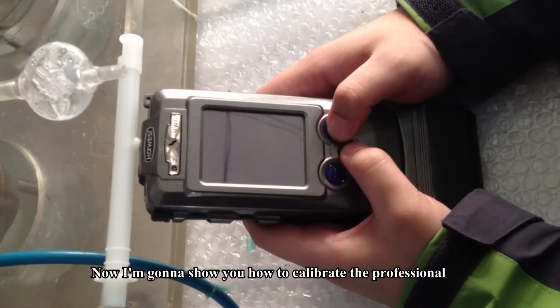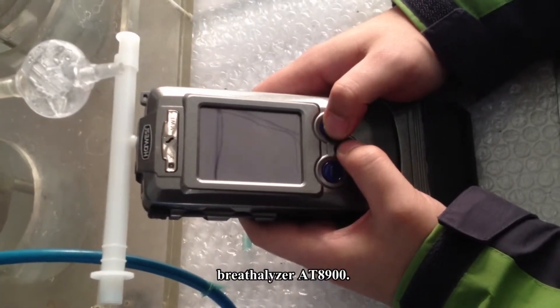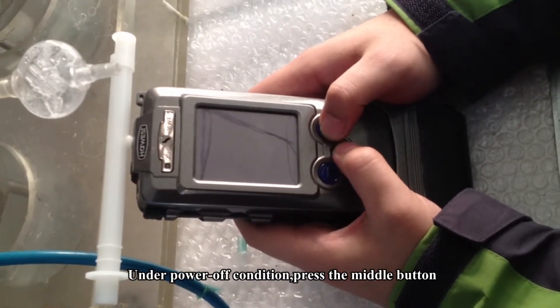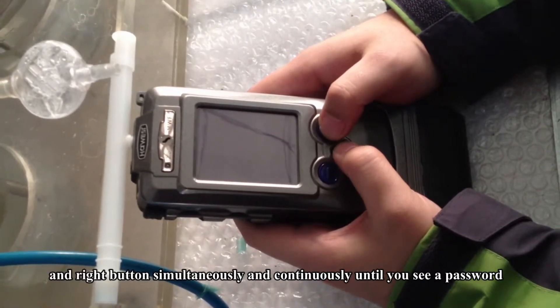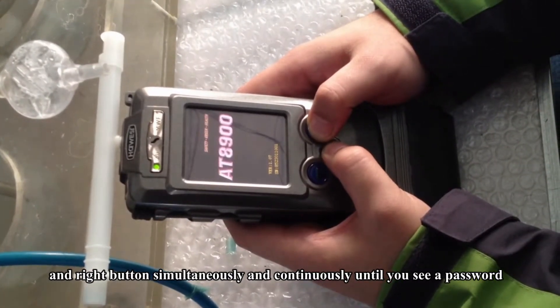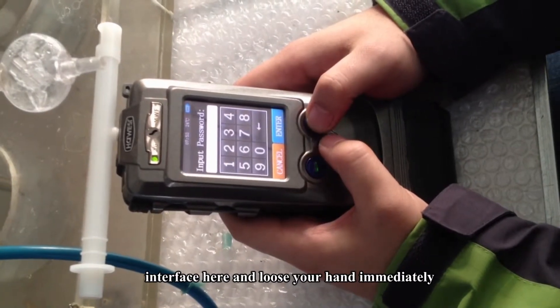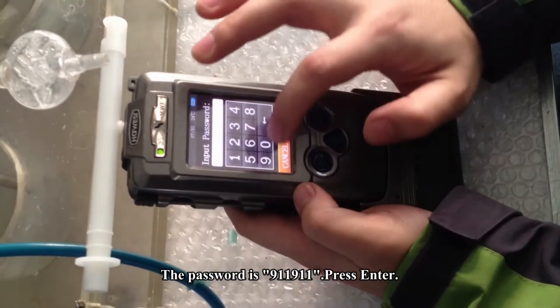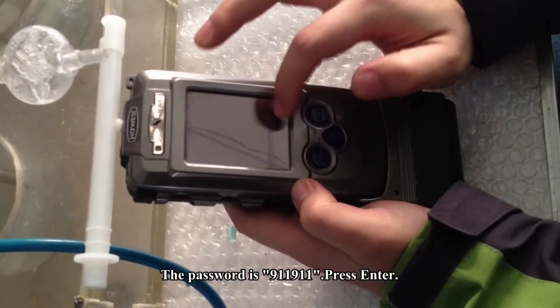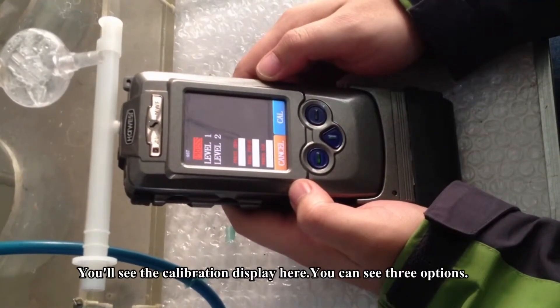Now I'm going to show you how to calibrate the professional breathalyzer AT-A900 under power-off condition. Press the middle and right button simultaneously and continuously until you see a password interface, then loosen your hand immediately. The password is 911911. Press Enter and you will see the calibration display.